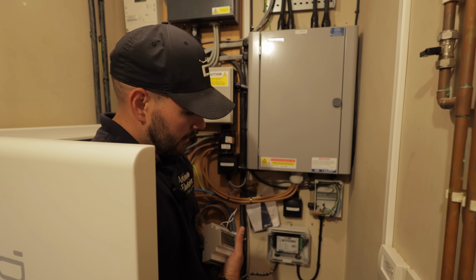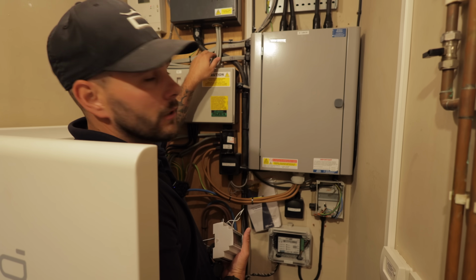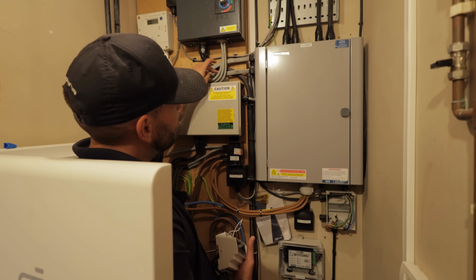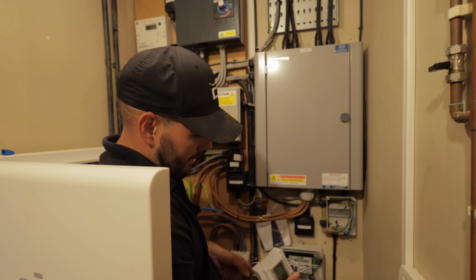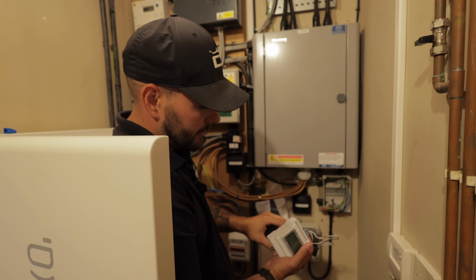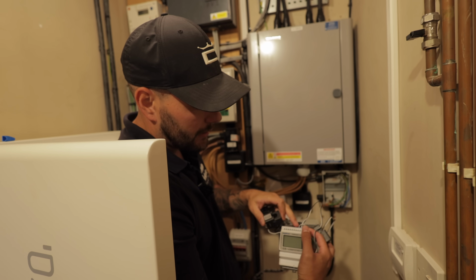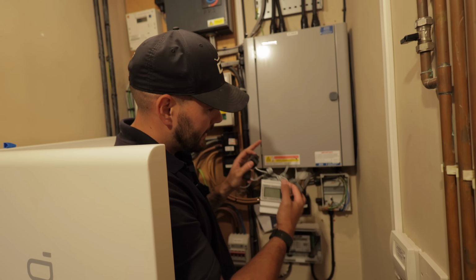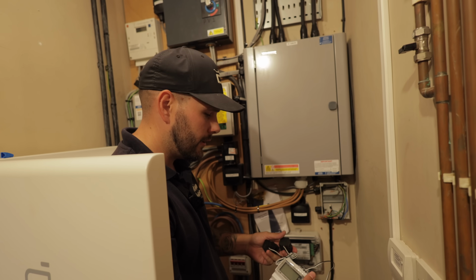And then from there we've got to get these CTs to go around the solar to monitor the solar. So we'll put those around here, L1, L2 and L3. And these are slightly too small, so I'm probably just going to have to extend them by cutting them here, taking these ferrules out, extending the cables just so they're long enough to reach down into that enclosure.